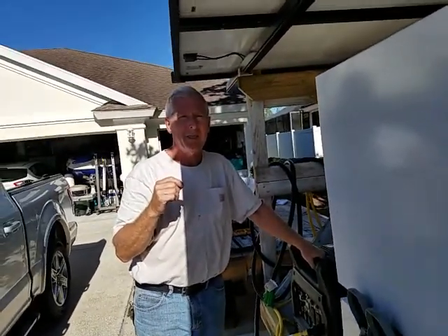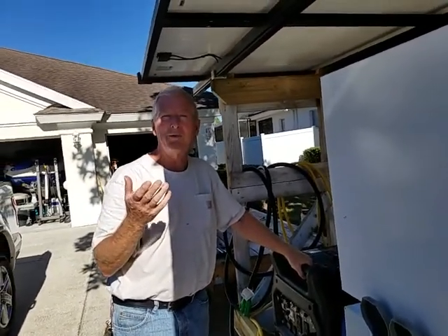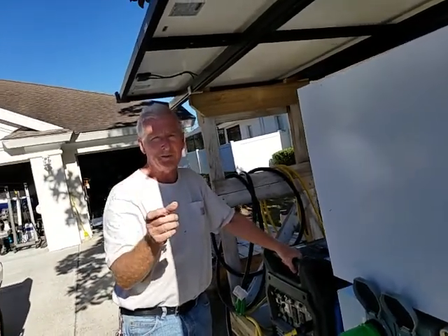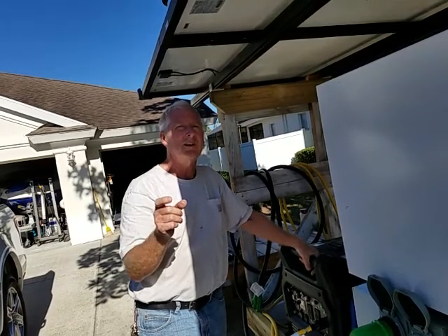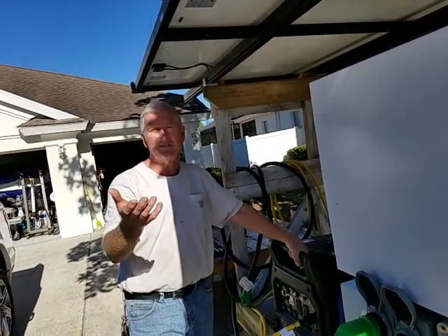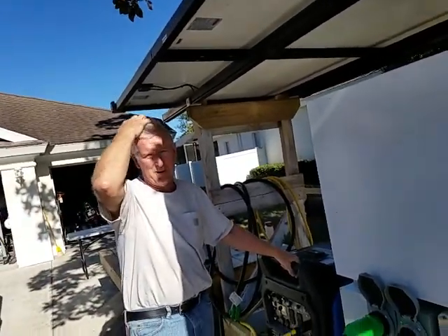Right. So if there was moisture or something that created an earth path, a parallel path through you, it's going to detect that because there'll be a differential between the energy that came in on the hot and returned on the neutral, and it's going to trip. And that's a human protection device. You'll find GFCI breakers in your kitchen and your bathroom, typically places where you might be wet.